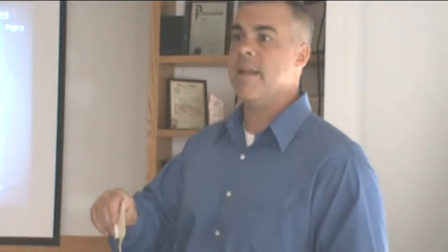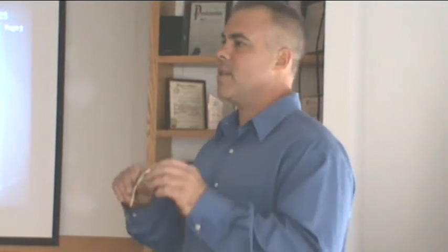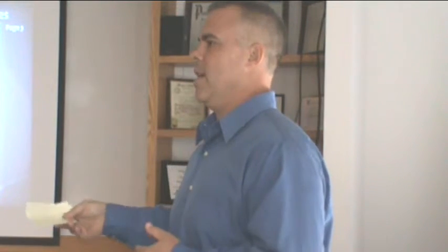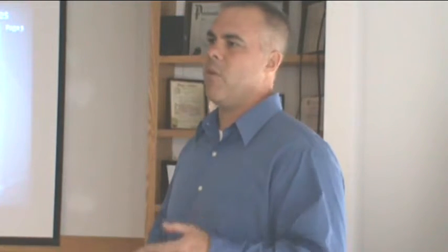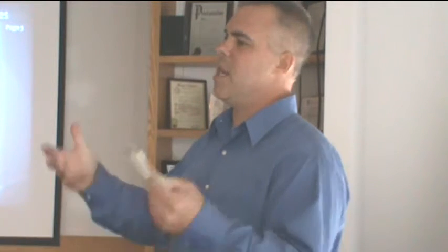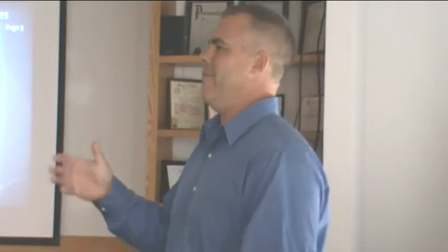What you can write is needs further evaluation or it's questionable. You can just honestly say, it doesn't look good, but it passed. And that's fine. Let the buyer and owner negotiate what's going to happen. So we've seen that before. We've run water, the trenches are getting completely full of water, and you think, man, 5 more gallons and it's up. Be careful. We don't want to be accused of something.